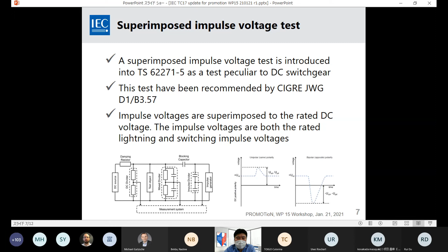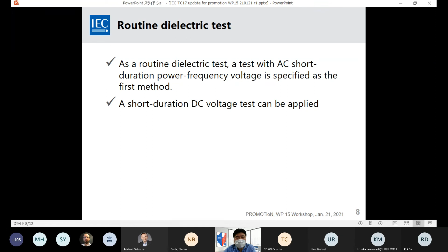Next is about the routine dielectric test. As a routine dielectric test, test with AC short duration power frequency voltage is specified as the first method. Of course, short duration DC voltage test can be applied.